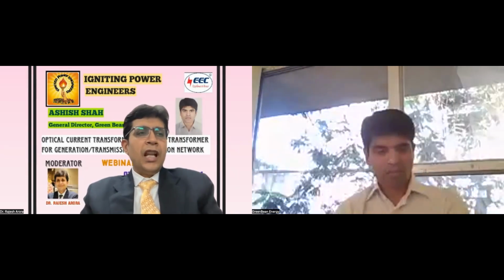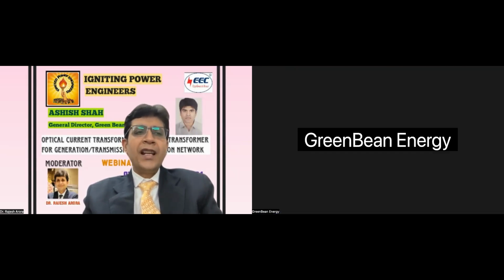Dear all, it is known to everyone that CT, PT, VTs are very important and critical components of any network, be it generation, transmission, distribution, any industry, solar PV system, hospitals, any other RE network. When we say CT and VT, they are used mainly for metering purpose and protection purpose, and presently both are governed by IEC 61869. CT and VT have many cores and ratings depending on the voltage systems and the requirements.